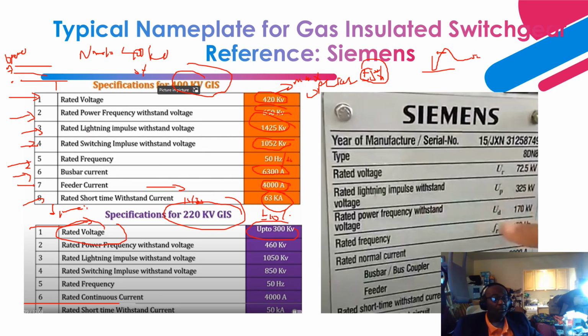For the rated power frequency withstand voltage, we have 460 kV, and like I said, the power frequency withstand voltage comes into play when we have an external fault. After clearing, it results in overvoltage. Or if you have a load rejection, that can result too. Or if you have a no load condition, which can also cause an overvoltage condition. So the GIS insulation system and components have been built to withstand this power frequency overvoltage condition.